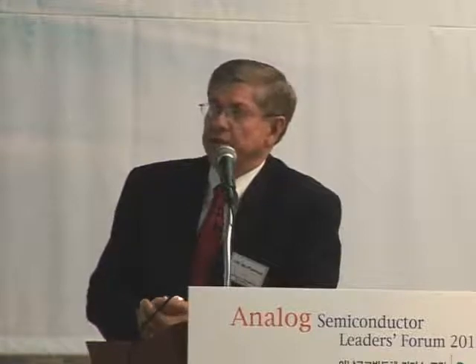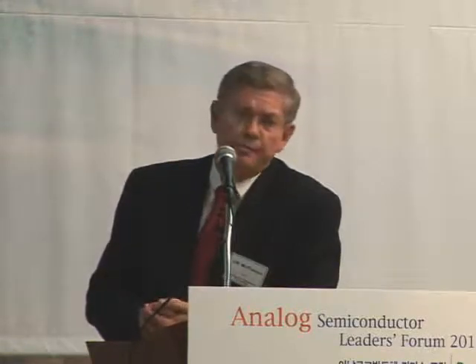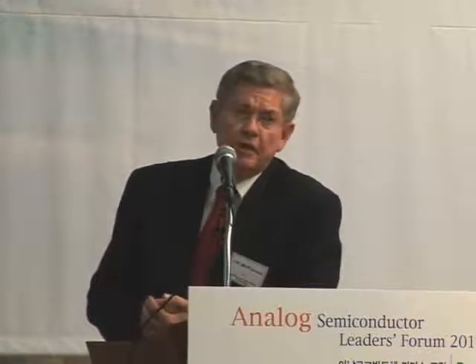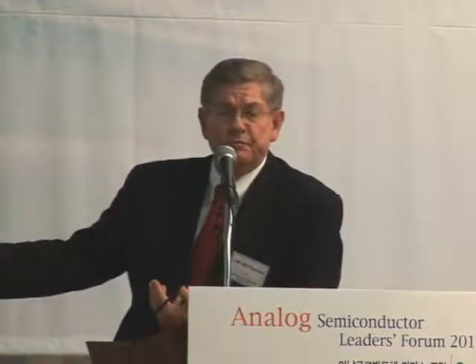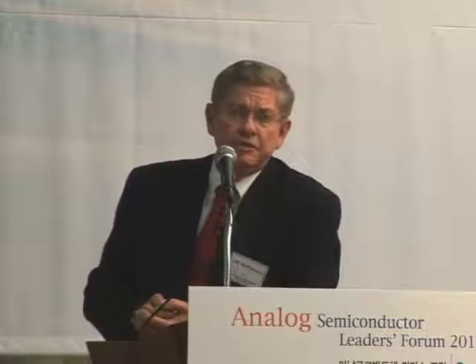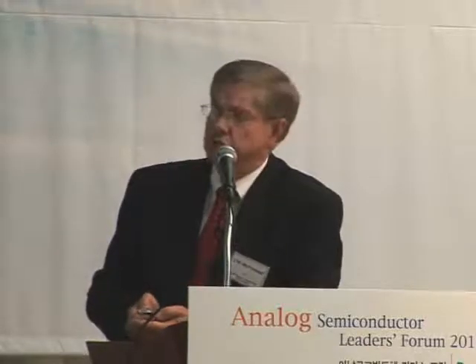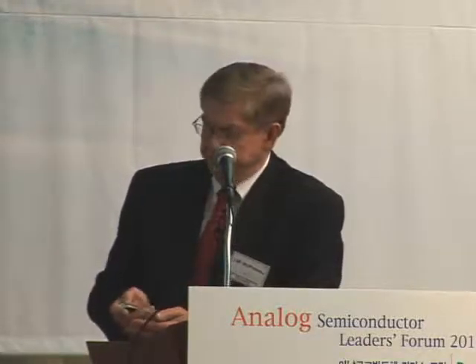Generally when these high voltage devices fail, remember the melting temperature of aluminum is only 660 degrees, while silicon doesn't melt until you get to 1410. So it's not the silicon being damaged, it's usually the metallization.